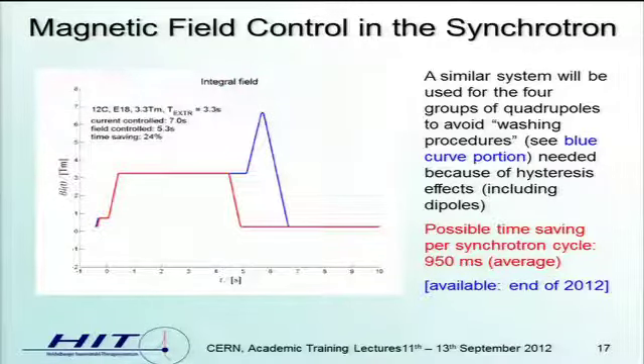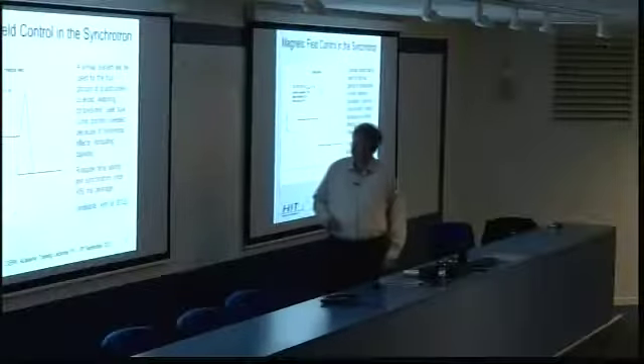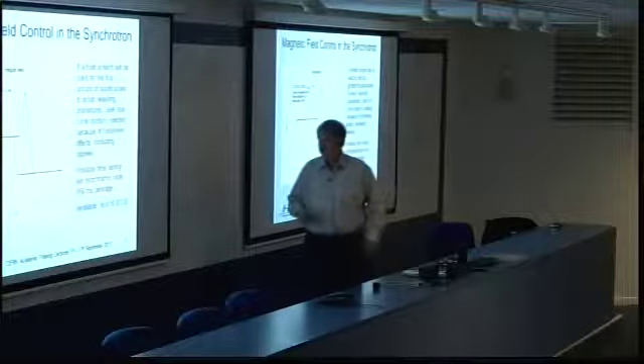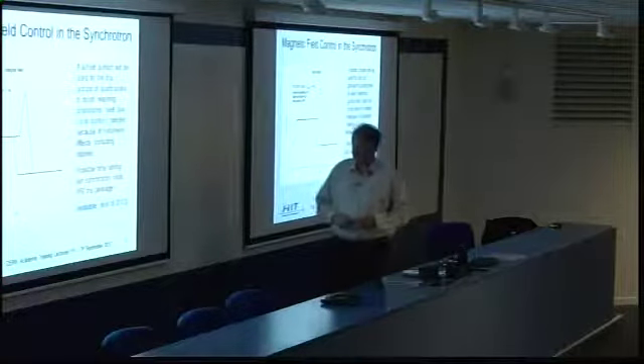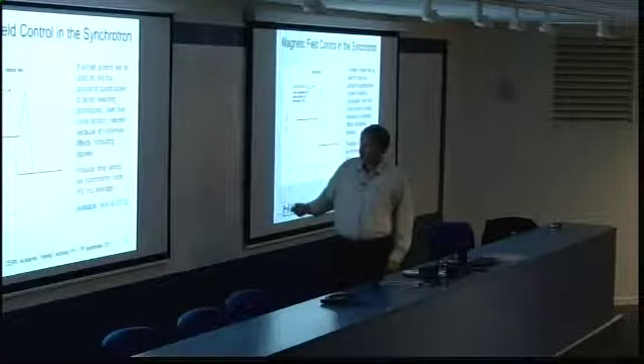When you look to the normal synchrotron cycle, what we have to do at the moment is not to have only the red curve, so we have to make a washing procedure, as it is called in accelerator slang. So we go to the saturation just to get rid of hysteresis effects. This is not only for the dipoles, but especially also for the quadrupoles. We have to do that, otherwise we never would have a stable beam at the treatment place. The height and the length of this part of the curve depends clearly on the energy that you have to achieve for the actual slice you irradiate. But the time savings overall would be 950 milliseconds, as we have estimated.